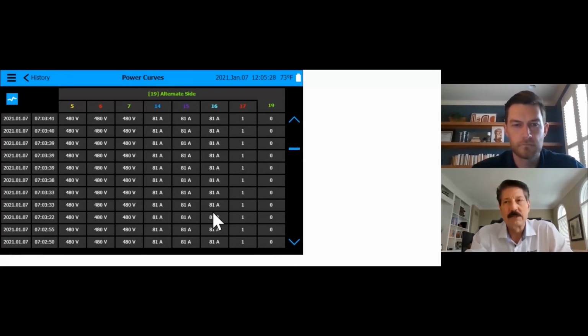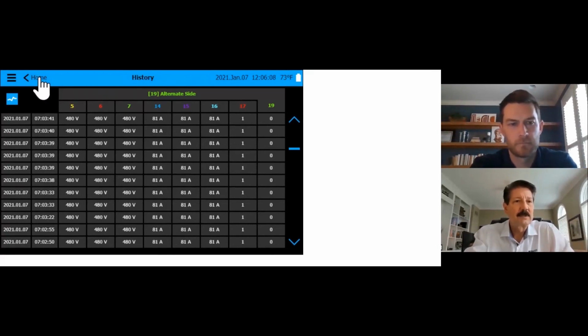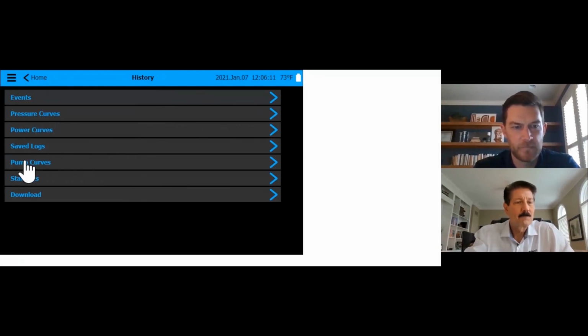This has happened before. We had a motor single phase. It drew 10 times, 12 times the current it was supposed to on 1 phase only. And its single phase shorted out and it damaged the controller and burned the motor up. Well, this data proved, number one, that when this occurred on C phase, the voltage from the utility dropped from 480 down to the low 300 volt range, 312. Because the current went up, the voltage went down. But we never single phased from the utility. And we tracked this until it burned out. It was something that actually shorted out internally in the motor. And this spreadsheet proved that. So data is really good for troubleshooting. It's an exceptional amount of information you have.